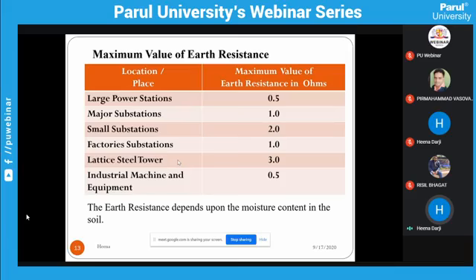Now, small substations mean your kV is below 110 kV, meaning 66 kV, 33 kV, 11 kV. For all these kVs, the earth resistance is 2 ohm. Now, factories and substations, different factories such as chocolate factories and other factories, their earth resistance is 1 ohm. Now, steel towers, meaning your transmission line towers, which carry power from one substation to another, have 3 ohm. Now, industrial machines and equipment, their earth resistance is 0.5 ohm. The earth resistance depends upon the moisture content in the soil.